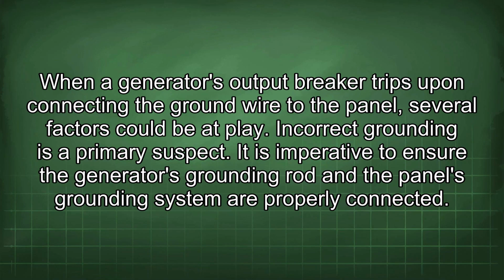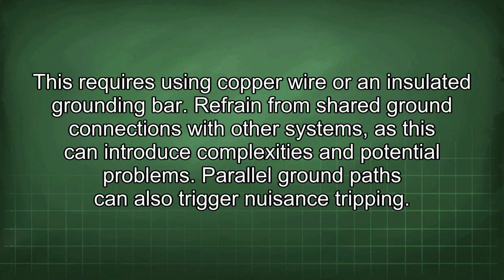When a generator's output breaker trips upon connecting the ground wire to the panel, several factors could be at play. Incorrect grounding is a primary suspect. It is imperative to ensure the generator's grounding rod and the panel's grounding system are properly connected. This requires using copper wire or an insulated grounding bar. Refrain from shared ground connections with other systems, as this can introduce complexities and potential problems.